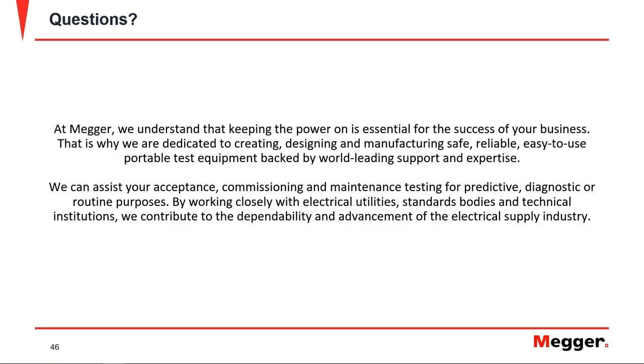The other option is that if you have that curve on paper for the breaker you are testing, you can contact us, and if you can share a PDF or a scan of that TCC curve, we'll digitize it and send you back a file that you can import, so that you will have that in the library. So again, the immediate answer is to use the generic option of the software. And if you test that type of breaker frequently and need it in the library, we can add it if you can share a PDF or a scan of the curve.